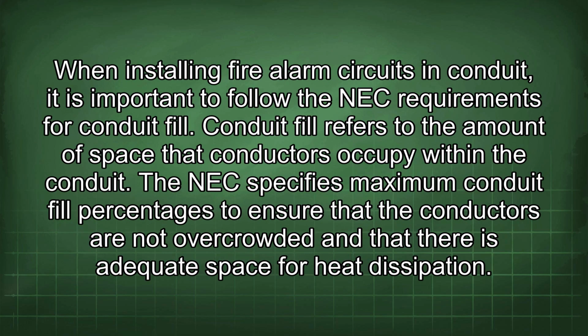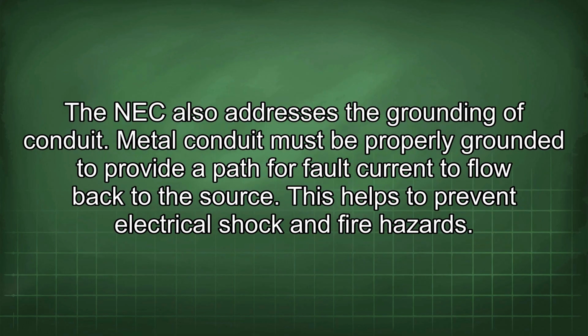When installing fire alarm circuits in conduit, it is important to follow the NEC requirements for conduit fill. Conduit fill refers to the amount of space that conductors occupy within the conduit. The NEC specifies maximum conduit fill percentages to ensure that the conductors are not overcrowded and that there is adequate space for heat dissipation. The NEC also addresses the grounding of conduit.